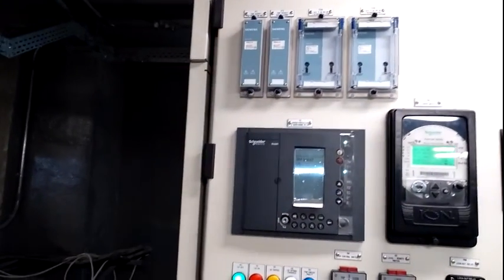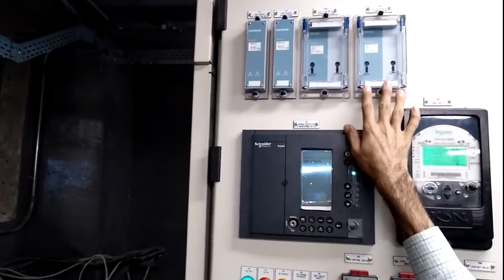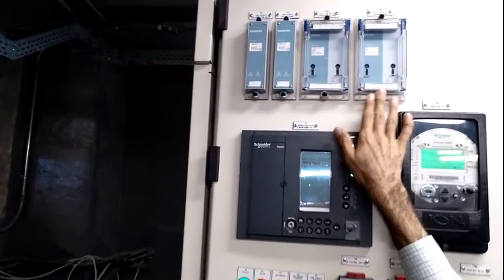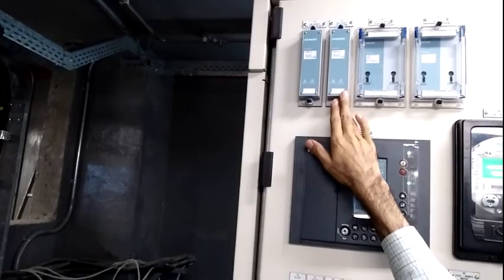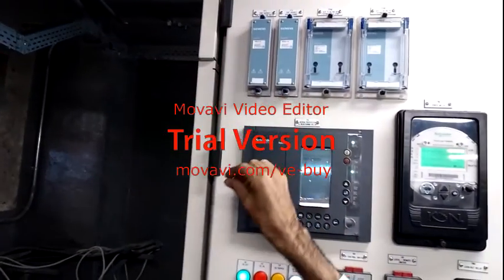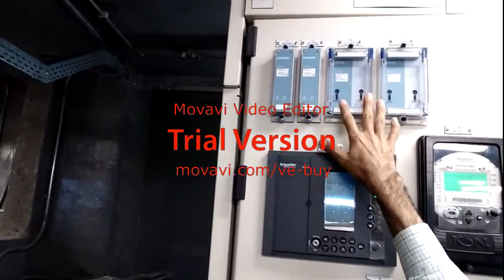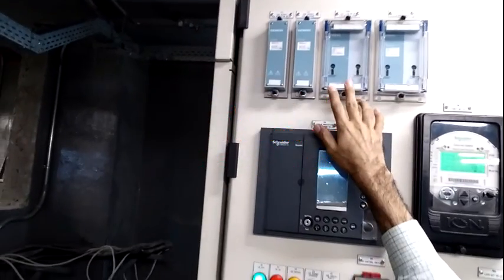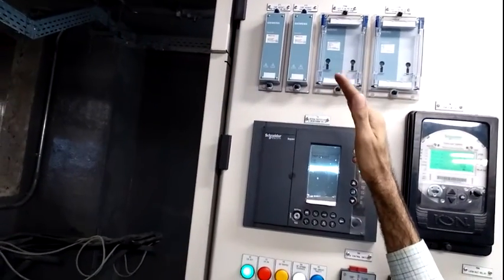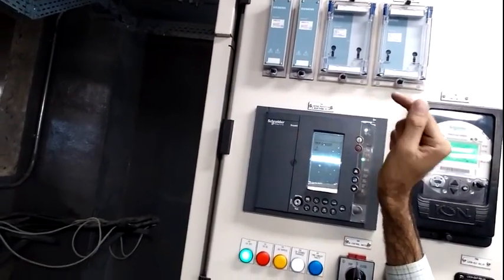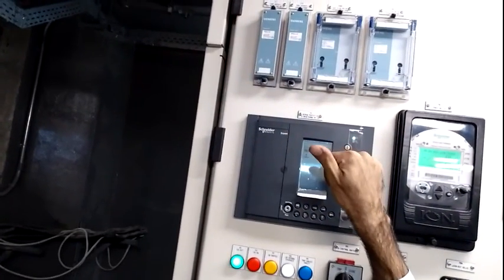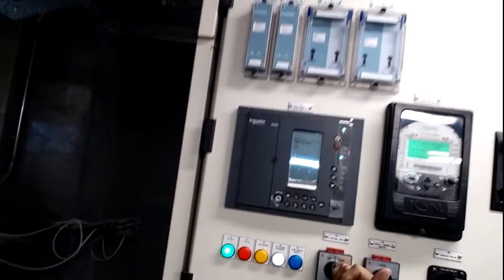These two flags are for tripping, and this relay contact is used for DCS signals, and this auxiliary we use for the DC control circuit and for breaker tripping. As mentioned here on this flag, if the breaker is tripped in condition 1, the flag display shows the red flag. That means your breaker is tripped, and you reset the flag and reclose the breaker. This one is tripping 1 and this one is tripping 2.